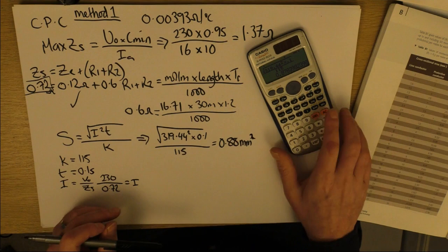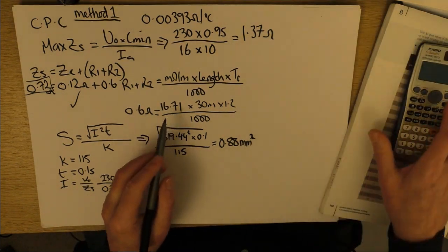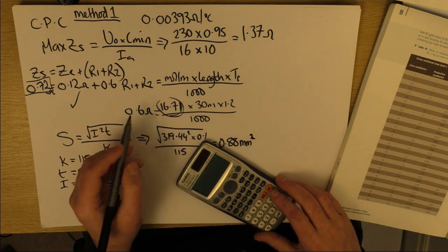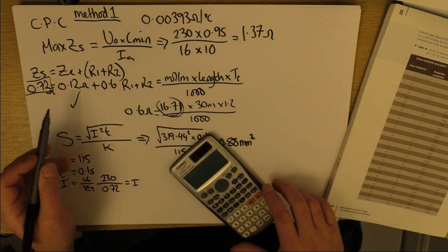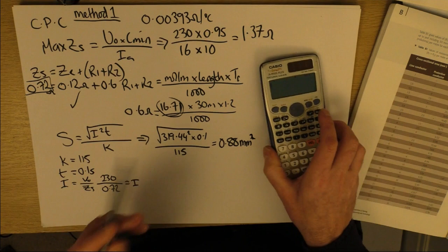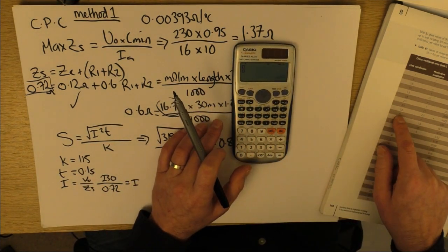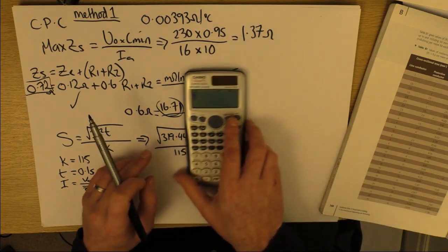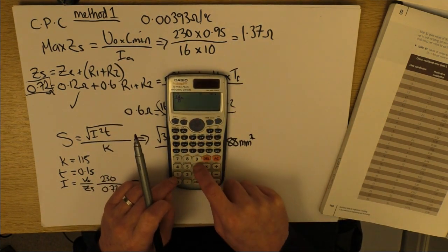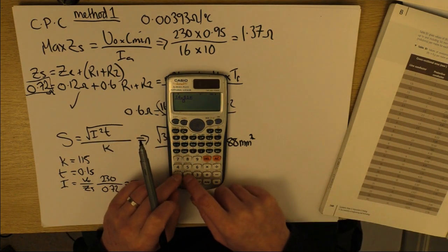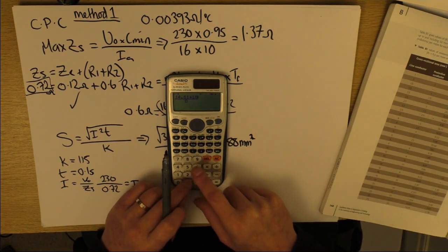I wonder if the 1 mil would have worked. Let's just give that a quick whirl. So we've just got to replace that to get a new R1+R2, new ZS, new fault current, and then plug it in. So, 1 sec. So 4 mil, 4.61, that's the 4 mil, and then the 1 mil is 18.1.